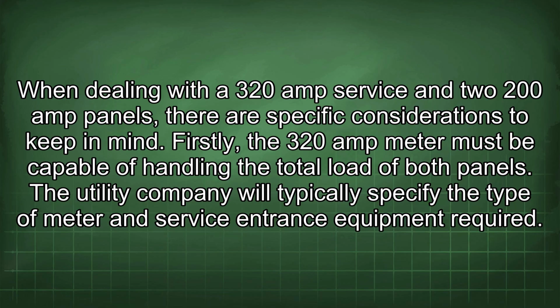When dealing with the 320 amp service and two 200 amp panels, there are specific considerations to keep in mind. Firstly, the 320 amp meter must be capable of handling the total load of both panels. The utility company will typically specify the type of meter and service entrance equipment required.